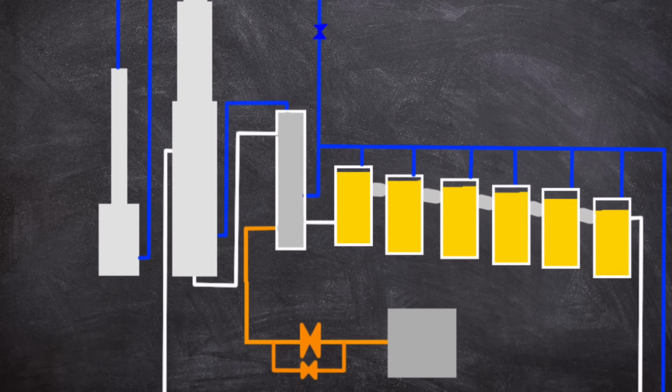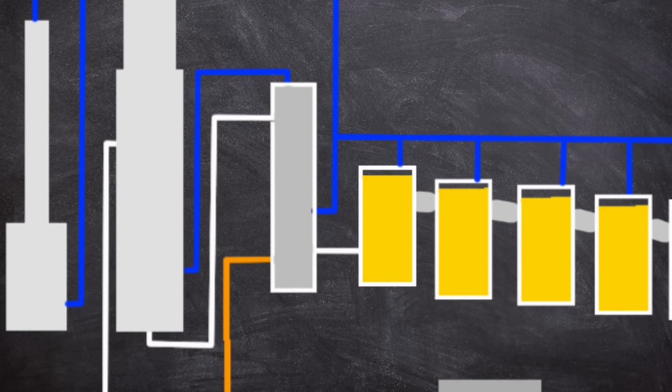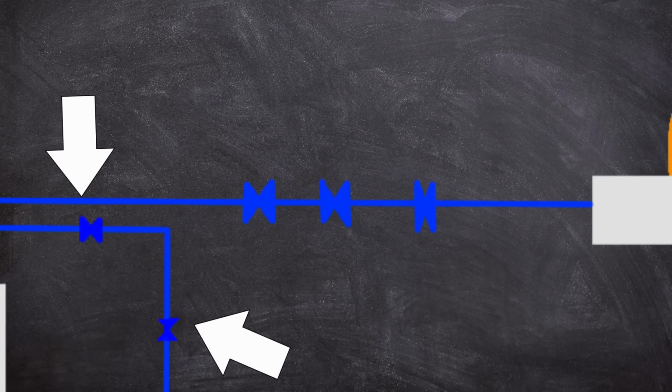To heat up the cyclohexane, a heat exchanger was used, and that employed steam. The steam flow to the exchanger is controlled by a valve, which can be controlled manually by the control room or automatically. To bypass the valve, a block valve is provided. This was closed on startup, meaning the only way to avoid overpressure is through the safety valves or manual intervention.